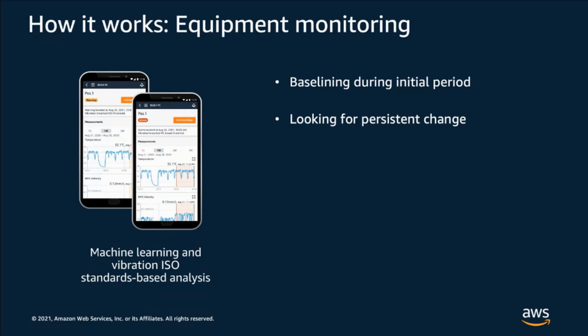The reason here is the application that Monitron is helping address is this application of condition monitoring and predictive maintenance. We see that anomalies that can persist indicate persisting conditions that are indicators of failure. And so by only alerting on these persistent anomalies, we are giving true indicators that require investigation and fixing. Based on the user feedback collected, Monitron retrains the model that was built during the learning period. This is an ongoing improvement that happens, and every time user feedback is received, the model is retrained.